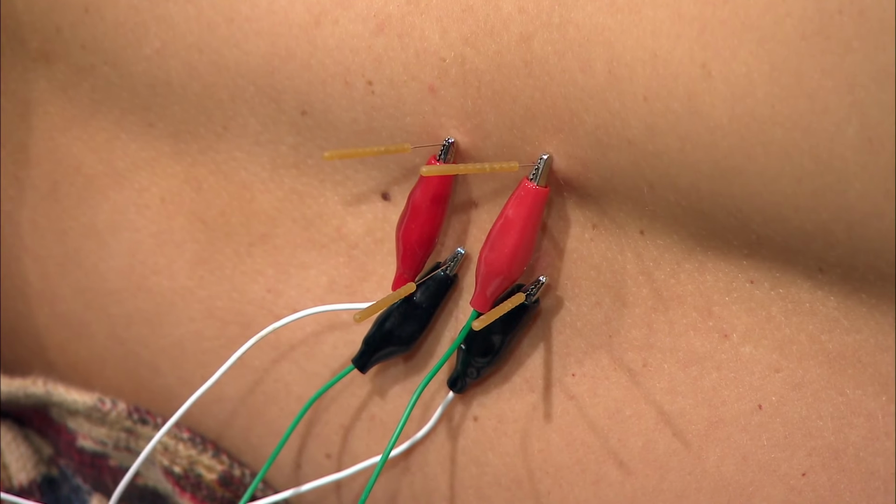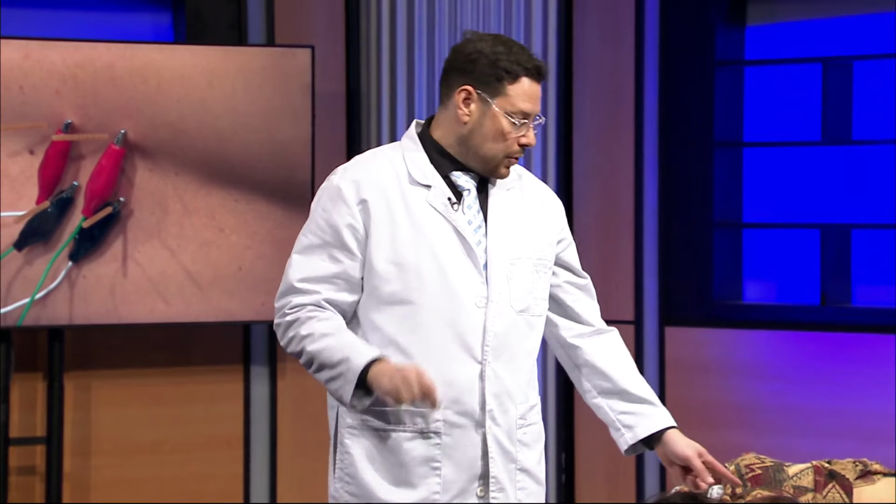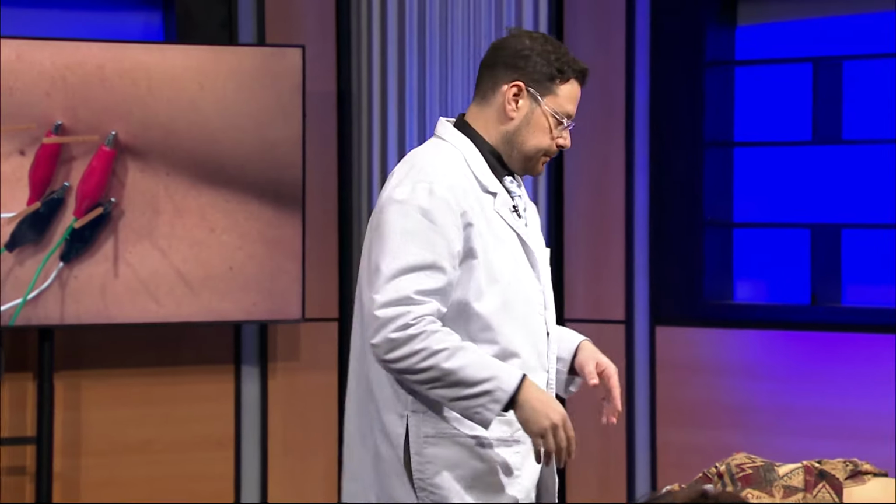A brand new battery, you'll have trouble dialing in a fast frequency because by the time they feel it, it's too much. So the amplitude knob goes from 0 to 10. I'm only able to get it to 2.5. Where if I had a half-dead battery, maybe I'd be able to dial in up to 6, 7, or 8 on that amplitude knob. It gives you a greater range of dialing in the power.